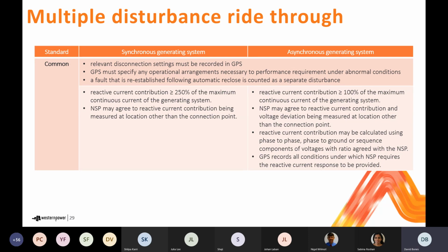And lastly but not leastly, there's a requirement that the GPS record all of those conditions under which the reactive current contribution needs to be provided from asynchronous generating systems. And so that might mean that if there's any particular need for the reactive current contribution to diminish under particular ambient conditions, then that would need to be captured and recorded in the generator performance standard.